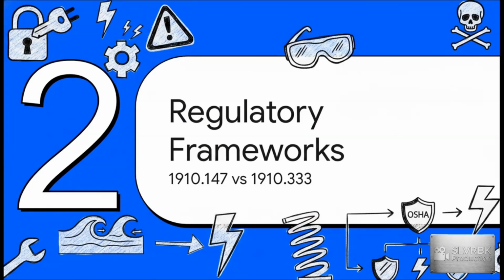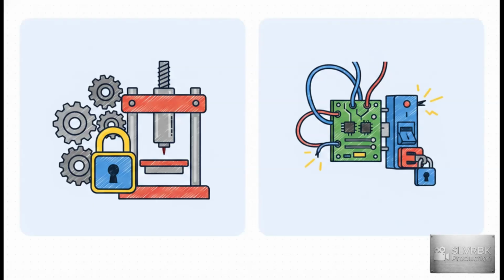Section 2. The frameworks. Let's look at 1910.147 versus 1910.333. Now you really need to know the explicit distinction between these two rules, because they do different things. 29 CFR 1910.147 is your broad general standard for the control of hazardous energy. It's designed to prevent the unexpected release of stored energies, mechanical, hydraulic, pneumatic, you name it. But, and this is absolutely crucial, 147 explicitly does not cover electrical hazards that arise from working directly on or near premise wiring and electrical conductors. Those specific electrical shock and burn risks are covered by 29 CFR 1910.333.